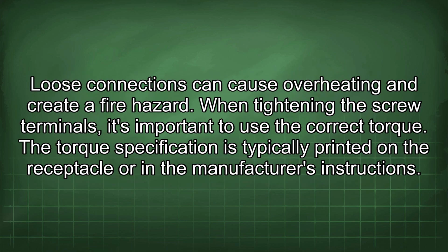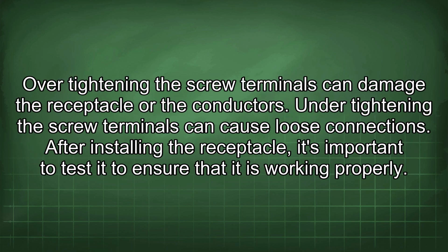Loose connections can cause overheating and create a fire hazard. When tightening the screw terminals, it's important to use the correct torque. The torque specification is typically printed on the receptacle or in the manufacturer's instructions. Over-tightening the screw terminals can damage the receptacle or the conductors. Under-tightening the screw terminals can cause loose connections.